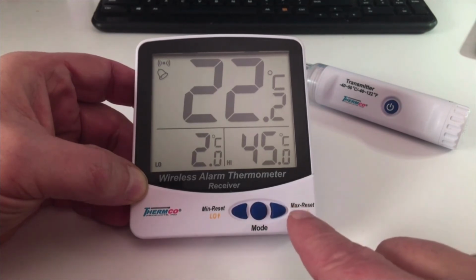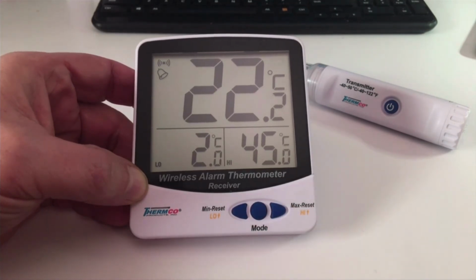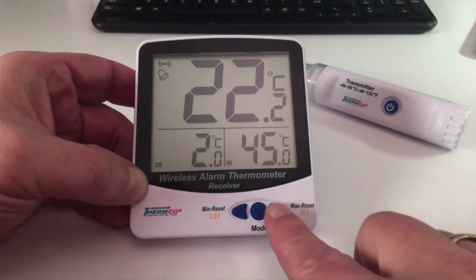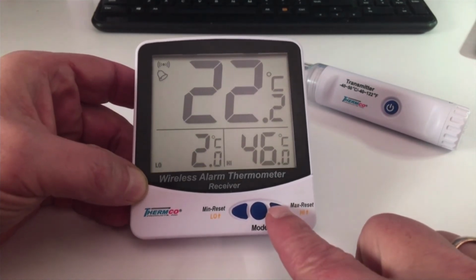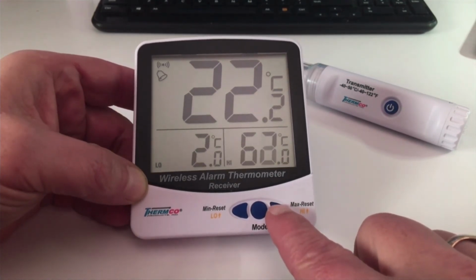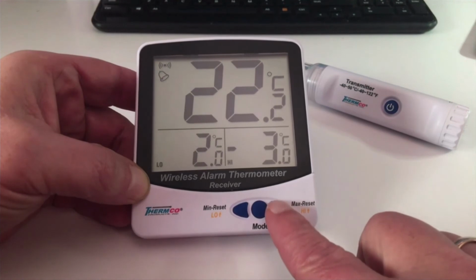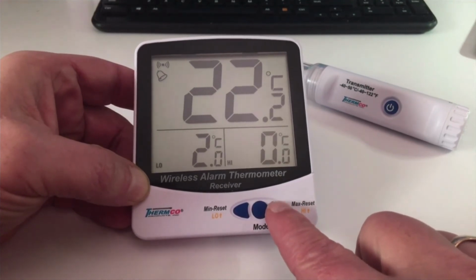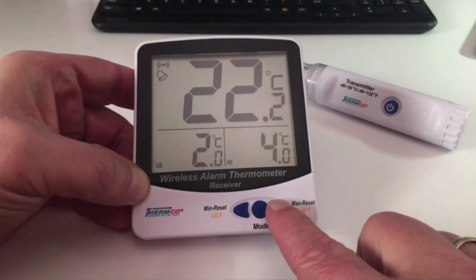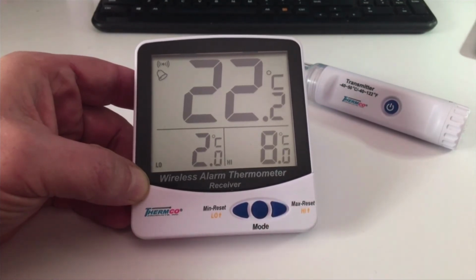So I hold this button until it goes up to the maximum value and it will loop back around. And then you'll see, I'll go up and around 70 degrees C, it will drop to minus 40. Now we're climbing back up. And when I get close, I start going single presses to get to the temperature. Okay, 2 and 8 degrees C.